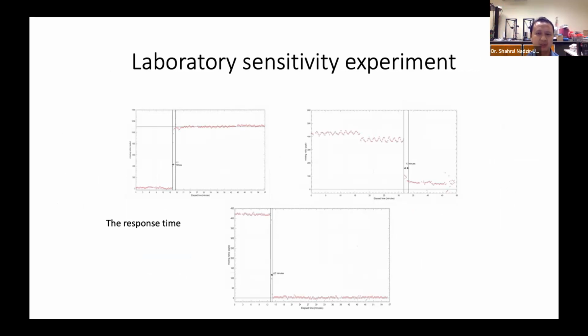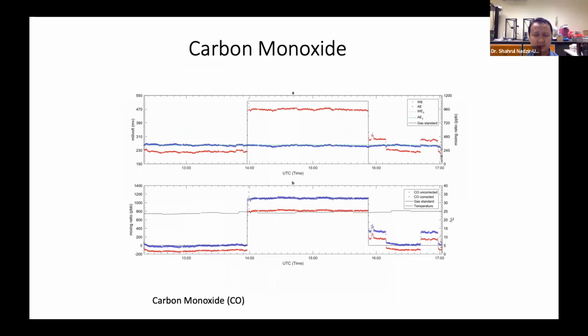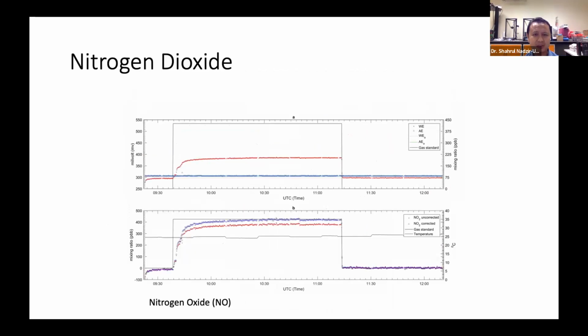We can see from this testing that AlphaSense has a good response towards different concentrations. You can imagine if you put sensors in the real field, and suddenly open burning reaches the sensor area, if you have insensitive gas sensors, they will not detect as fast as they can. So this is why the sensitivity lab experiment is very important. It is the same experiment we conducted for carbon monoxide, from zero concentration to high concentration, and to low concentration for nitrogen dioxide.